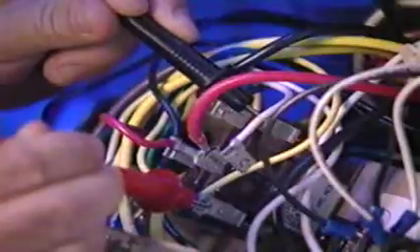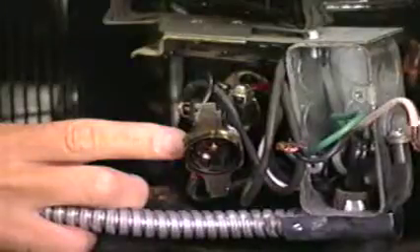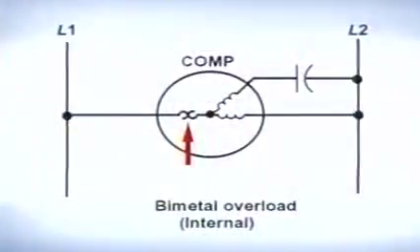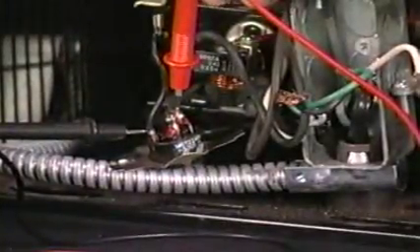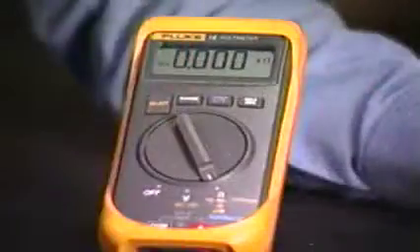Contactors cause sets of electrical contacts to open or close automatically to either energize or de-energize system loads in response to load requirements. The contactor coil can be open, shorted, or good. Similar to contactors, relays are also used to automatically control the operation of system loads and are tested in a similar manner. Overloads protect system loads from an overcurrent or overheating condition by opening the circuit that feeds power to them. Troubleshooting overloads can be done with an ohmmeter since these devices typically have only two wires.